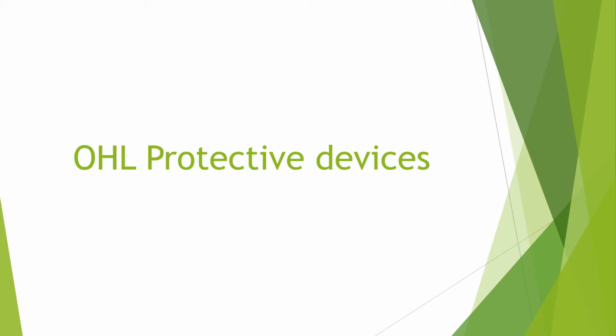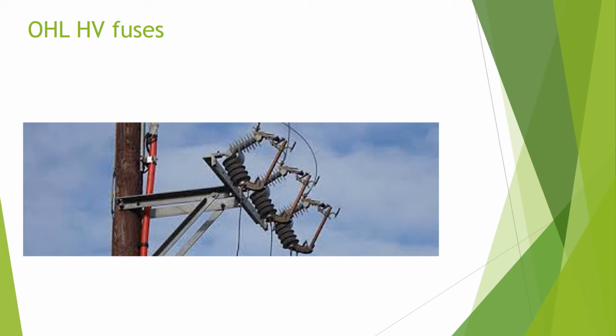Overhead line protection is provided in several ways. Overhead line fuses are usually of the dropout expulsion type. When an overcurrent flows through the fuse element causing it to operate, the fuse drops out of its fixed contacts but remains hanging. This allows easy fault location identification.